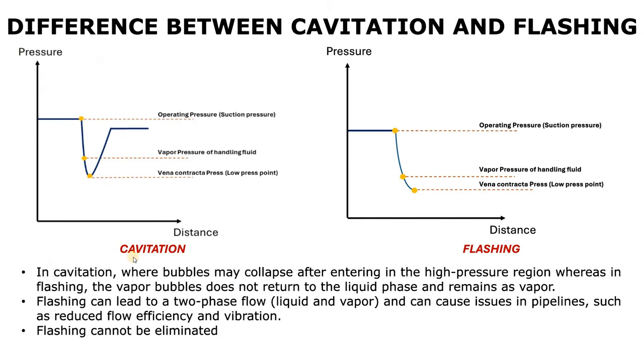Now let's look at the graph for cavitation. Your pump is operating at a certain pressure. There is a sudden decrease in pressure — for example, at the eye of the impeller. At this low-pressure point, boiling can occur. Then, as the fluid moves to the high-pressure region — because that is the work of the centrifugal pump — the void bubble is forced by the liquid and bursts. That is cavitation. Note that in cavitation, the pressure first drops then increases again.